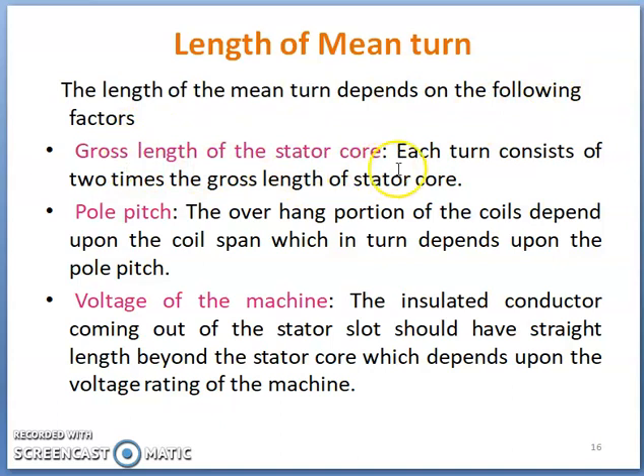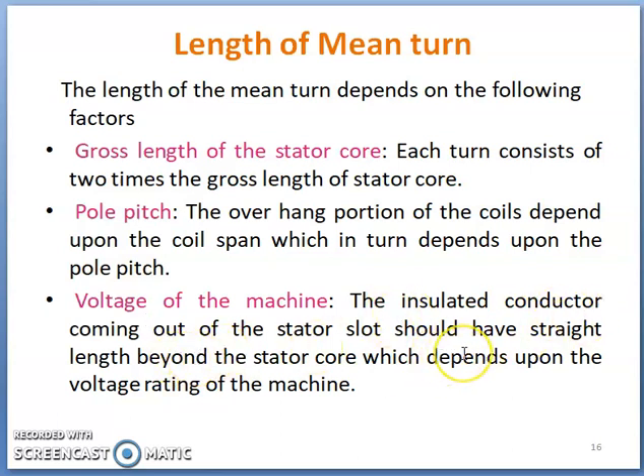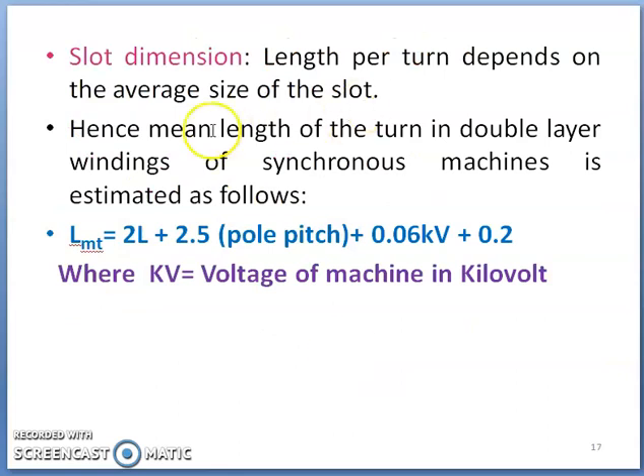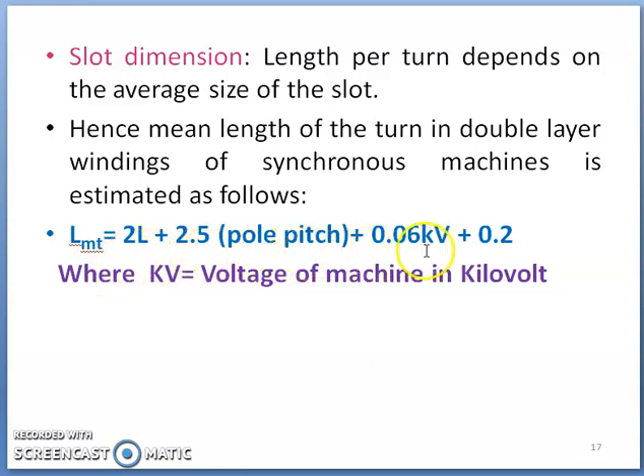The length of mean turn depends on the following factors: the gross length of the stator core (each turn consists of two times the gross length), the pole pitch (since the overhang portion of the coil depends on the coil span, which in turn depends on the pole pitch), and the voltage rating of the machine. The mean length of turn in double-layer winding of a synchronous machine is estimated using the empirical formula: LMT = 2L + 2.5τ + 0.06 kV.